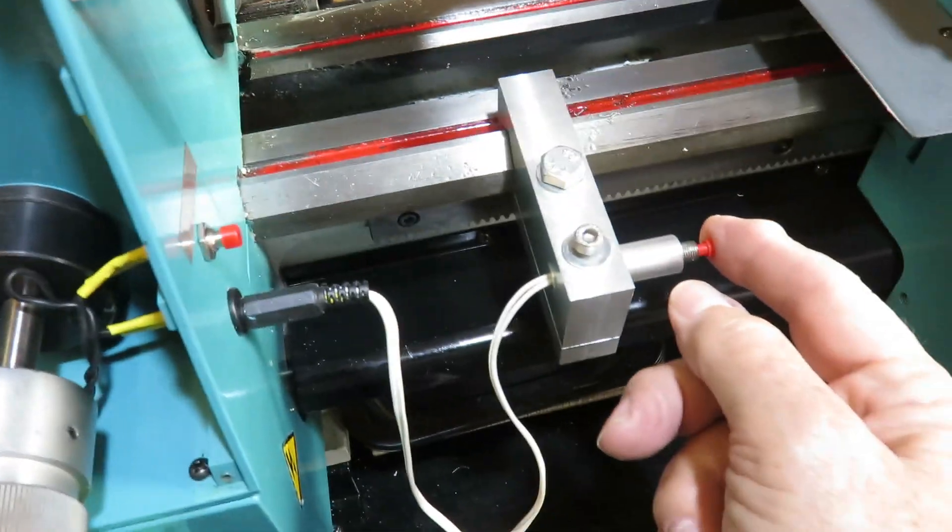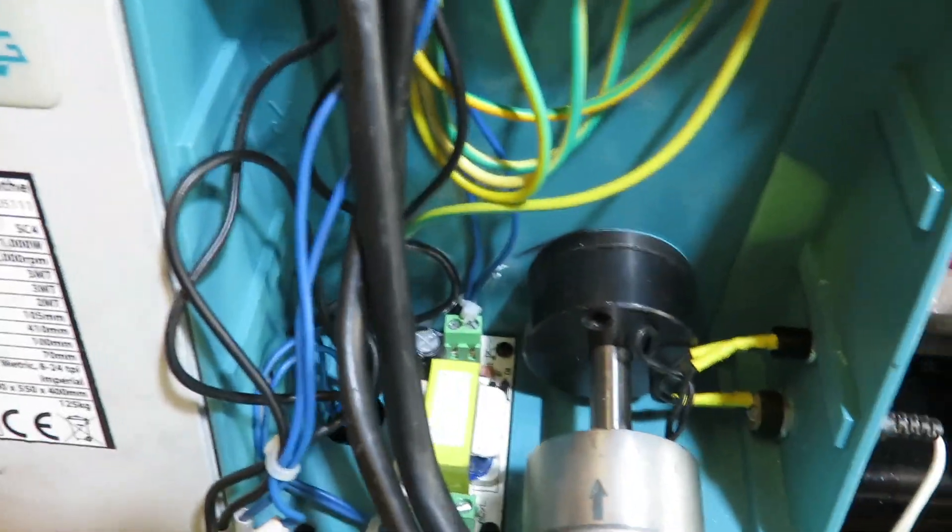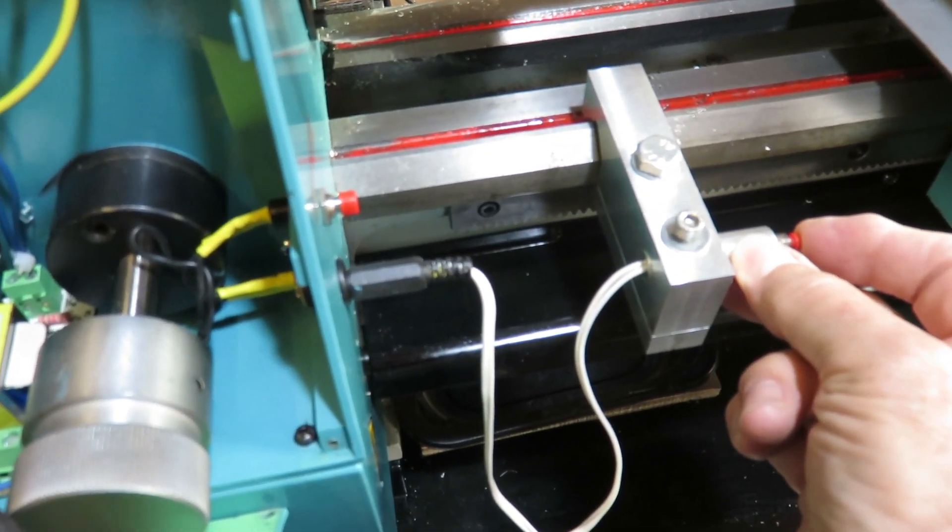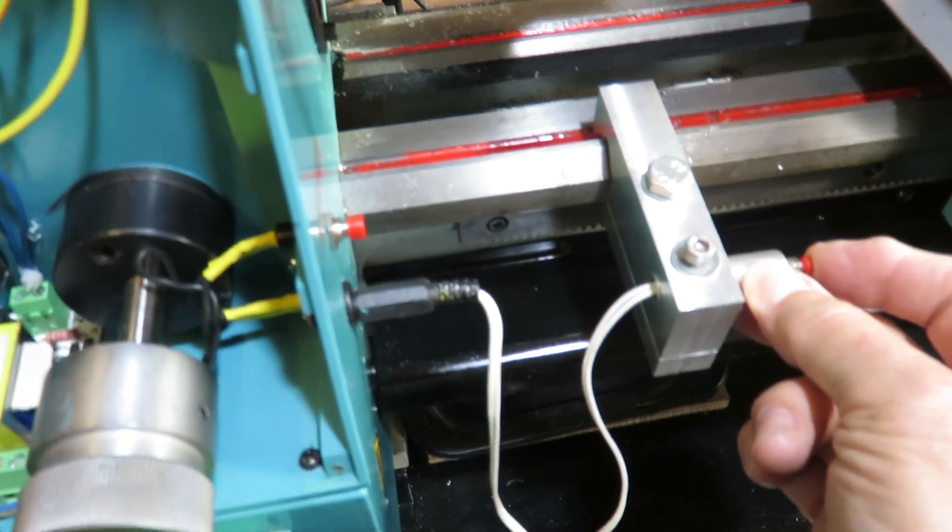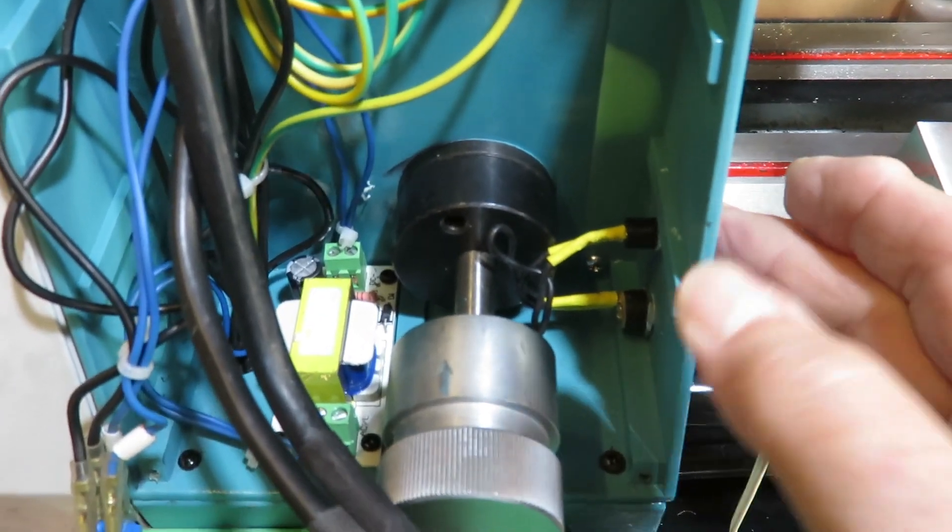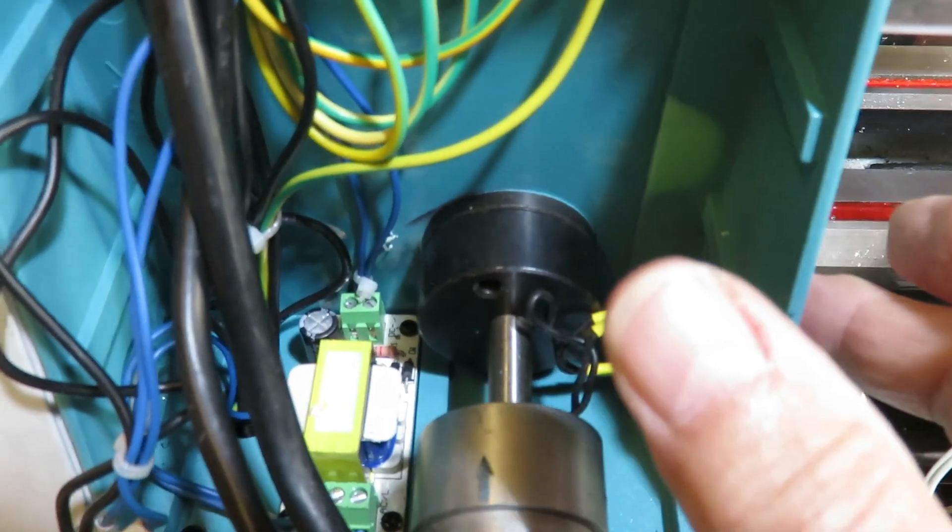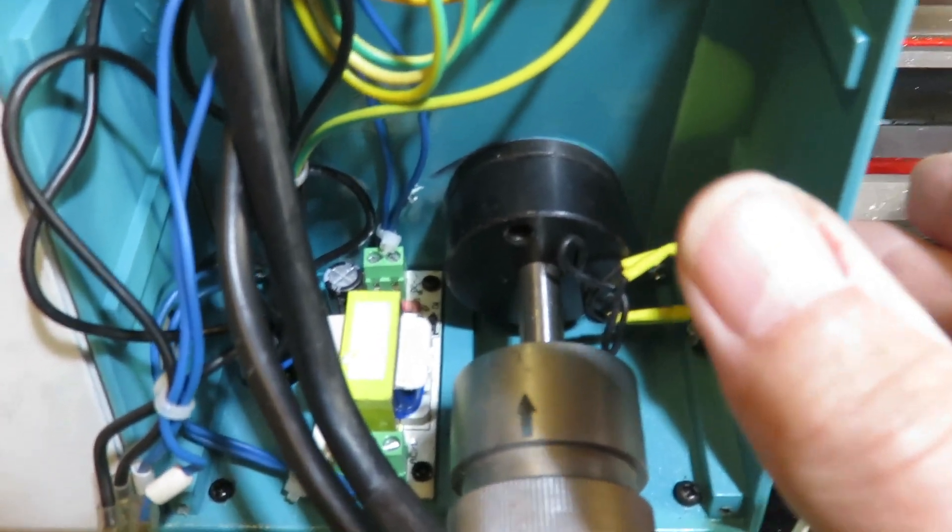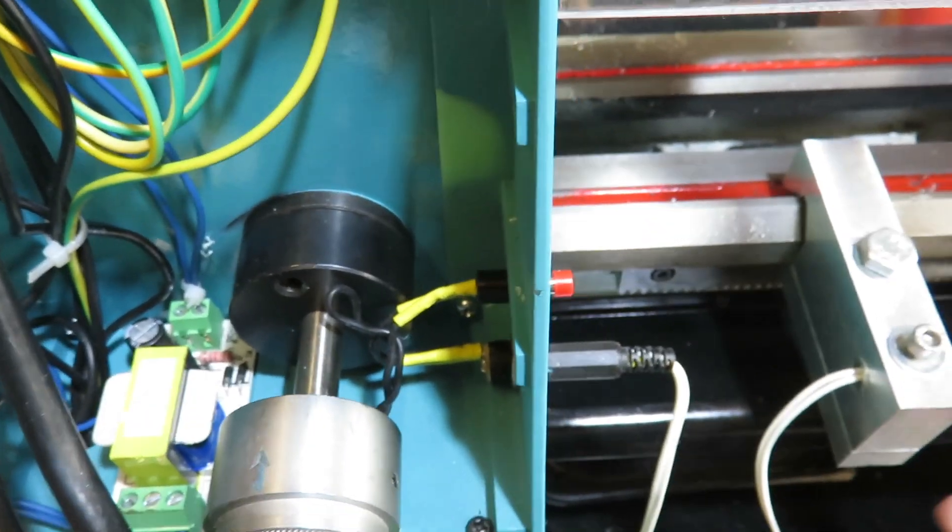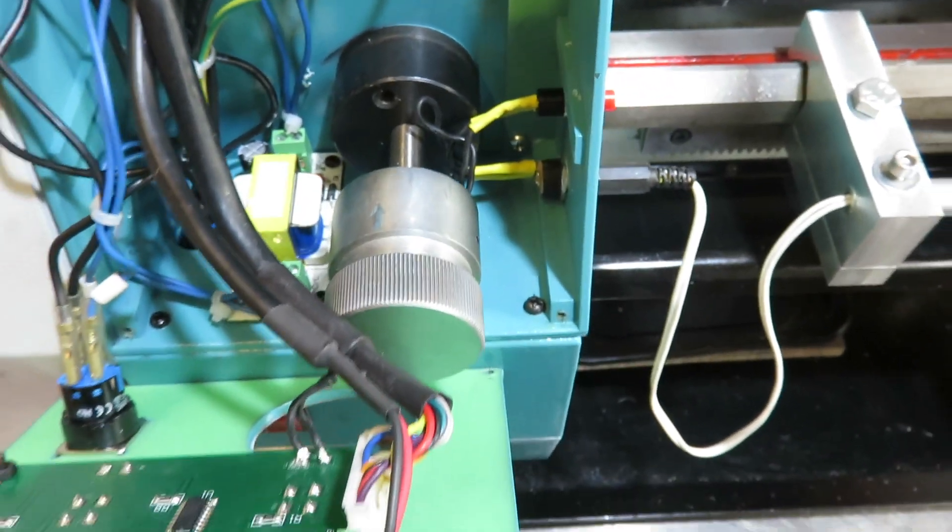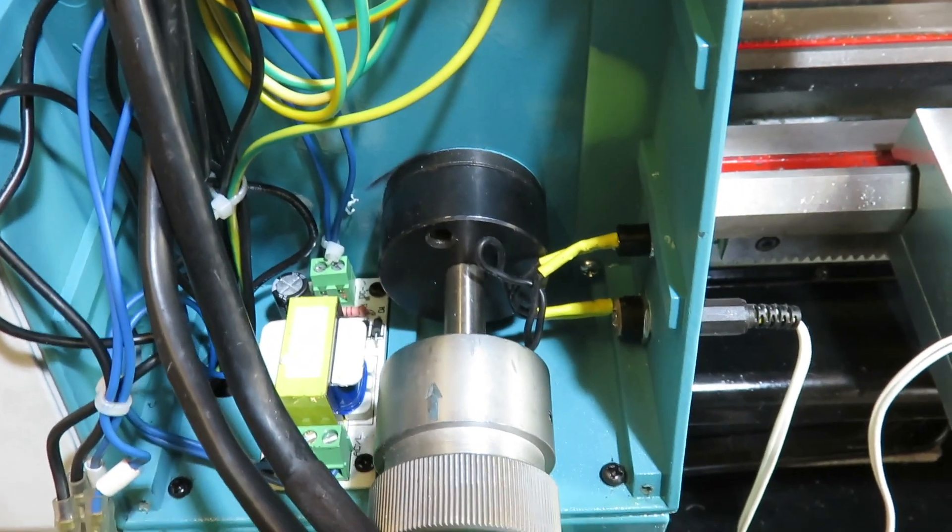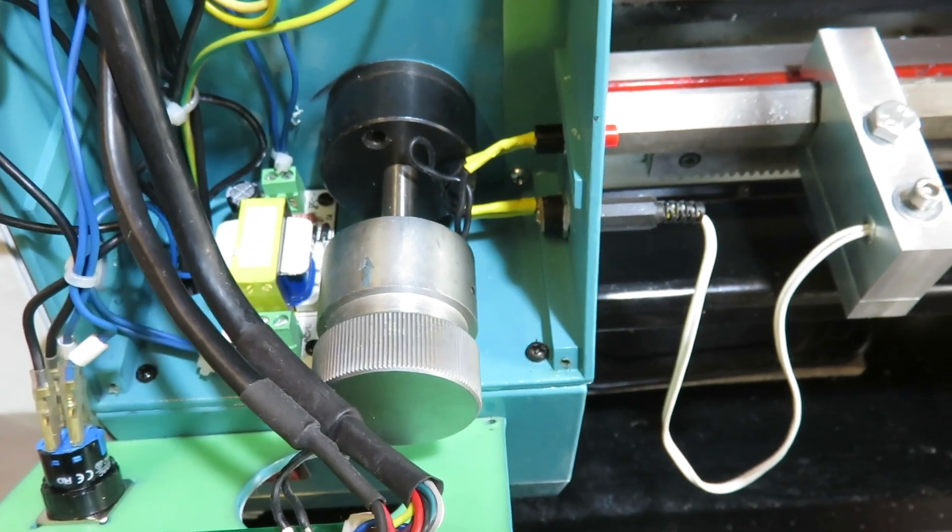Okay. This one is always open until you push it. This one's always closed till you push it. So as the carriage comes along and hits the button, it stops the motor. So it stops turning. What you do then is you press this button here, which now allows you to control use the front panel. You can now turn it into reverse and start it going. And once it started, you can let go of that button because now this is now opened up again. Does that all make sense? And I'll do a little circuit, show you a little circuit diagram, which I'll attach to this as well.